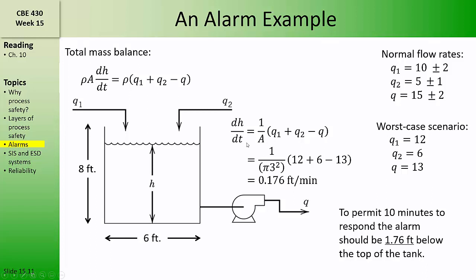Dividing the accumulation by the cross-sectional area of the tank, we find that at the worst-case scenario, the tank level rises by 0.176 feet per minute. Therefore, to permit 10 minutes for the operator to respond to the alarm, the alarm should be placed 1.76 feet below the top of the tank.